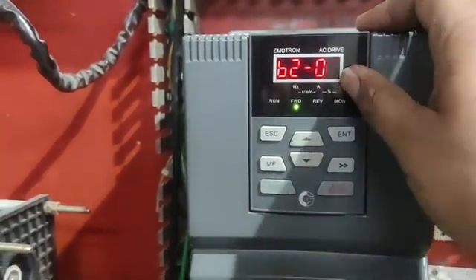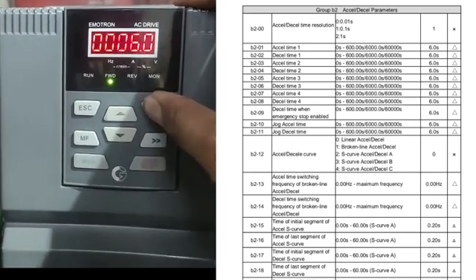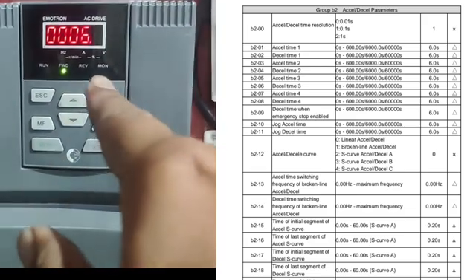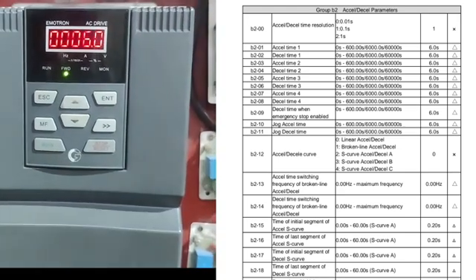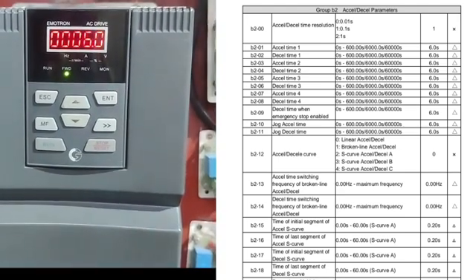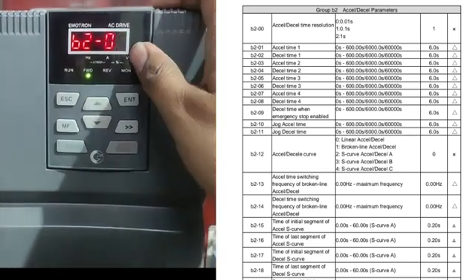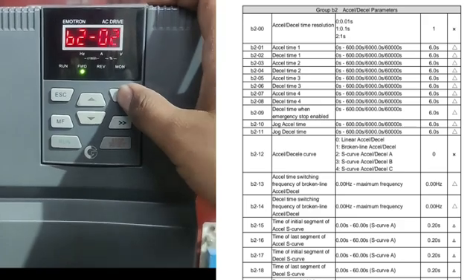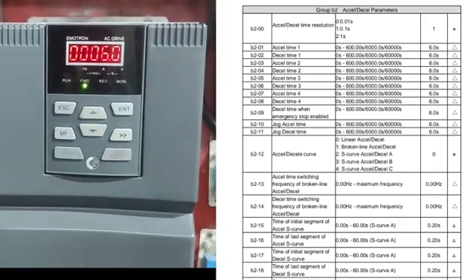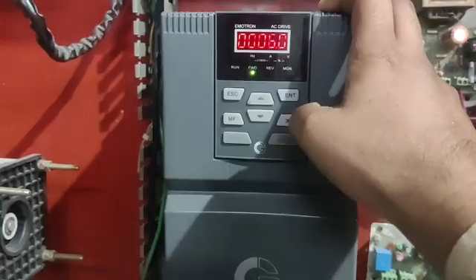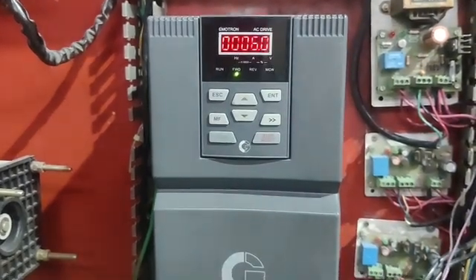Parameter B201 is Acceleration Time — when we start the drive, this is the time taken from zero frequency to maximum frequency. We set 6 seconds for acceleration time. Parameter B202 is Deceleration Time — when the motor is running at full frequency and we stop, this is the time taken from full frequency down to zero. We also set 6 seconds for deceleration time.